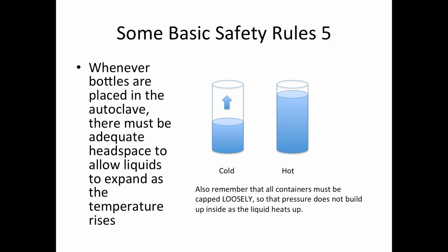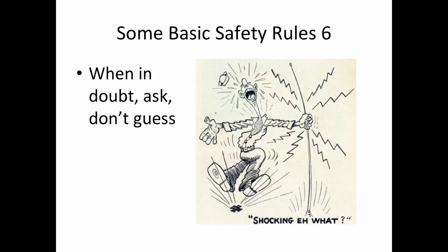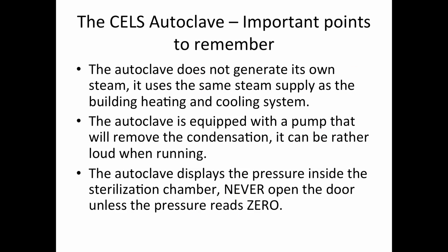Whenever you are autoclaving liquids, there always has to be adequate headspace to allow the liquids to expand as the autoclave temperature rises. And also remember that all containers must be capped loosely so that pressure does not build up inside as the liquid heats up. And the most important safety rule is, when in doubt, ask, don't guess. Let's talk about a few issues related to our specific autoclave in the CELS building.